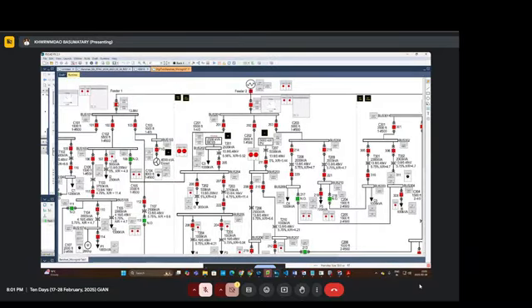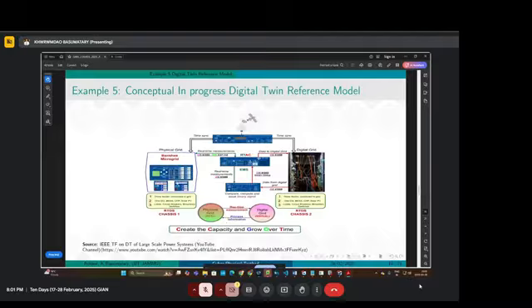Here, this feeder 1, feeder 2, and feeder 3, I have the actual SEL relays for feeder overcurrent protection. All this data, such as load, battery energy, resistance, breaker status, grid power, load active and reactive power, solar PV, and some critical parameters, has been taken to the RTAC controller.